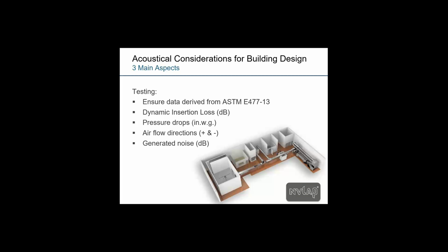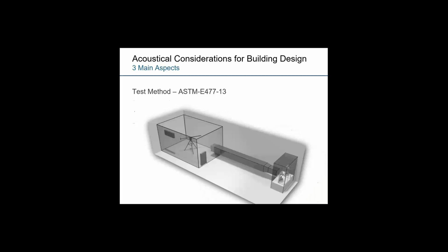In general, when testing silencers, there's a wide variety of noise control tests and procedures that are followed, and these are typically done for measuring what we call dynamic insertion loss. And I'll take a minute to walk through the test standard and the way the test is primarily conducted to give you maybe a better understanding of how this is obtained. In general, silencers are tested for, like I mentioned, dynamic insertion loss and pressure drop under laboratory conditions. And the way it's done is that, as shown here in this image, silencers are tested in a ducted configuration under a wide variety of configurations and sizes.